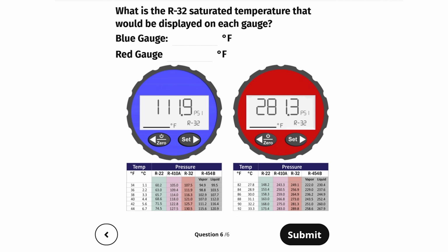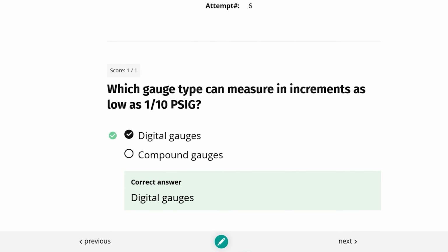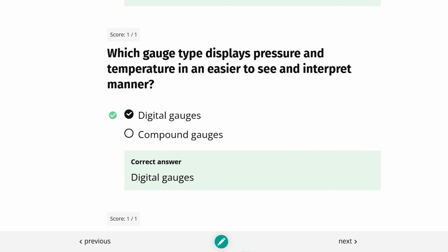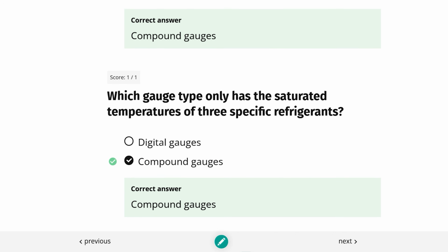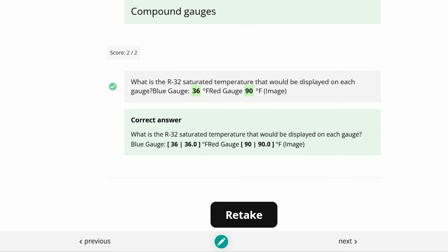adjustment screw. What is the R32 saturated temperature that would be displayed on each digital gauge? For the blue gauge, we look at 111.9 psi, and we line that up with the saturated temperature, and we find 36 degrees Fahrenheit. On the red gauge, we take 281.3 psi, we convert that to the R32 saturated temperature, and we find 90 degrees Fahrenheit. Then we submit our assessment and review our answers to see which ones we got correct and which ones we might have got wrong, and see why. After that, we're going to hit next and continue on.